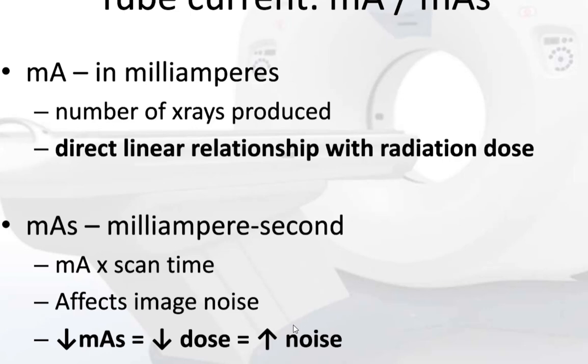We will start with tube current, or MA or MAS. MA is measured in milliamps. It is the number of X-rays produced and has a direct linear relationship with radiation dose. MAS is MA times scan time. It affects image noise, so if we decrease MAS, we will decrease the dose and increase the noise.